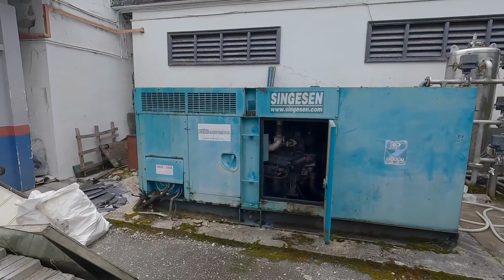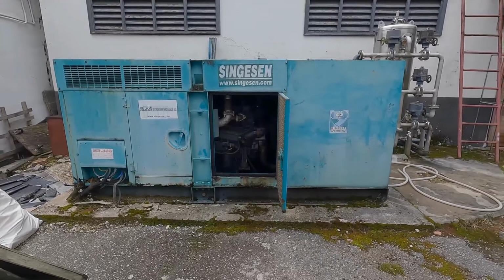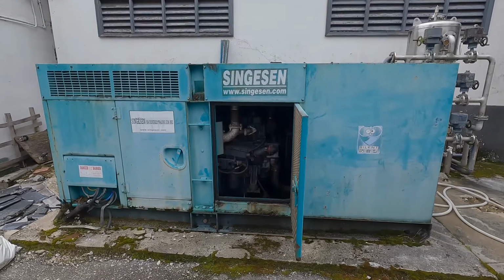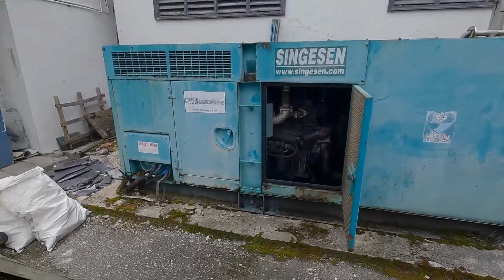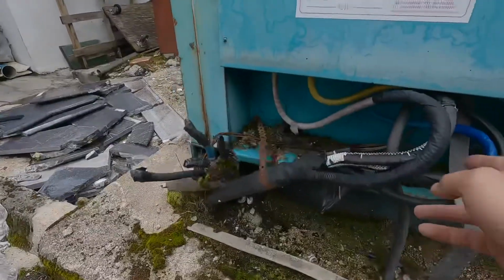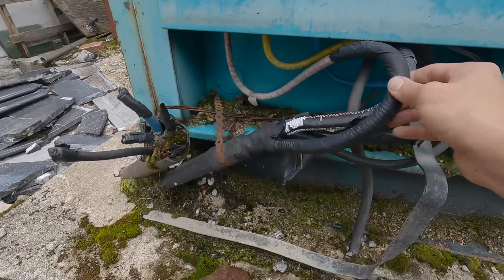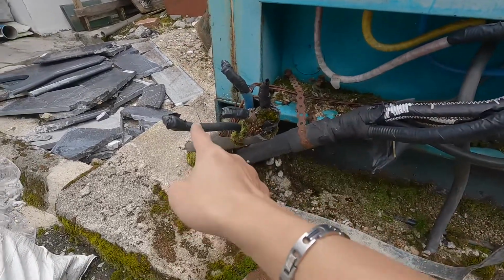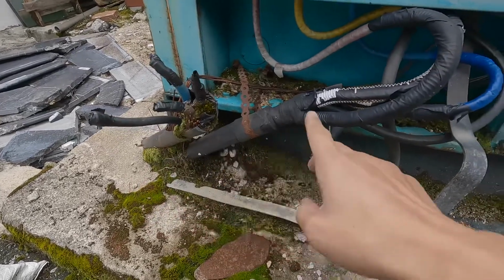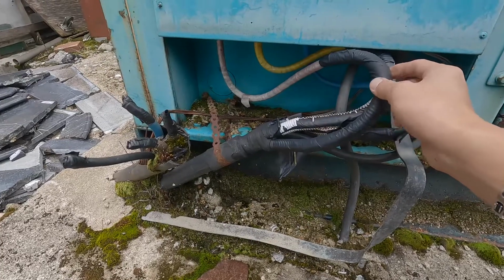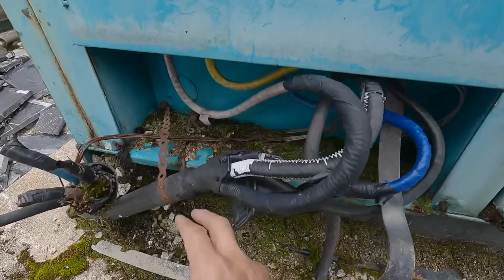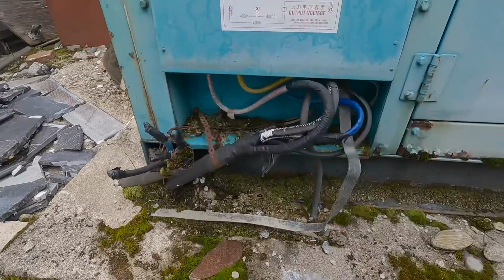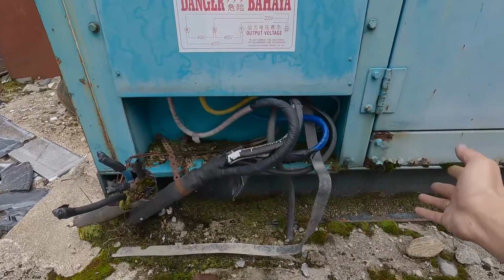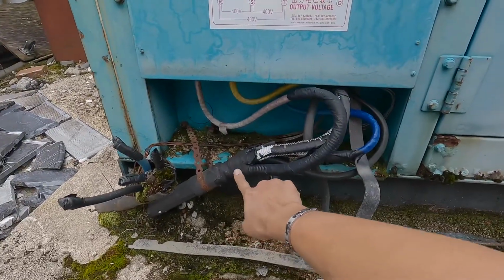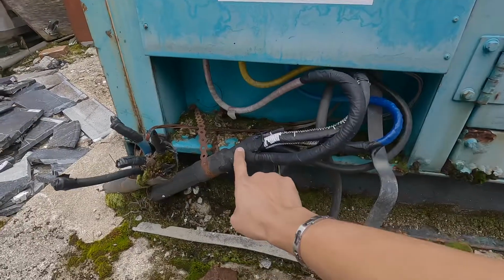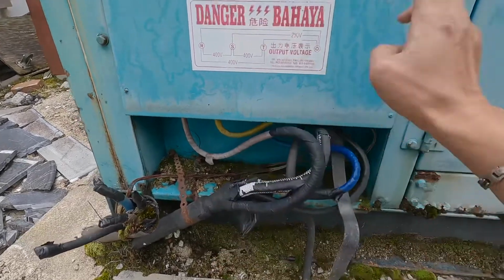This is a compact mobile genset. From the info I get, this genset is to back up the essential supply inside. Let us take a look at whatever we can see here. From here we can see this outgoing cable is quite corroded and damaged, and previously this cable also had problems, so they cut it off already and did another new cable. This new cable is also not properly installed, because as I see here, it is only taped with PVC tape. By right, it should have a metal enclosure to cover and protect from weather and rainwater, because this part is not weather sealed. Rainwater can seep in over time. This is one thing.